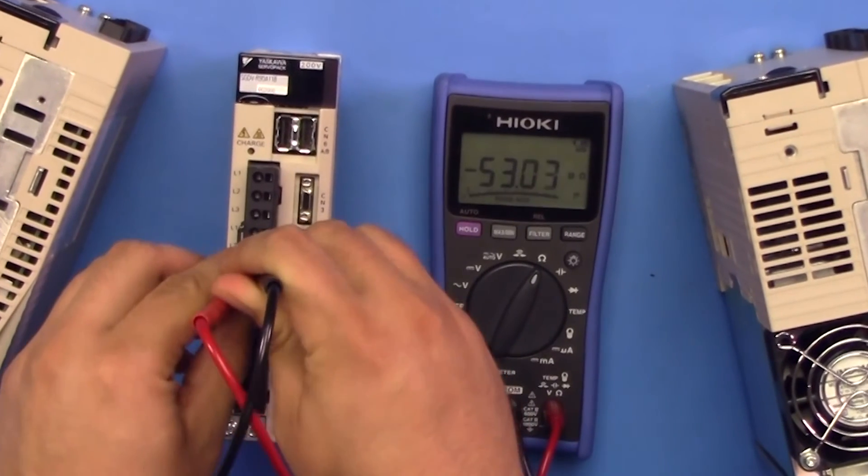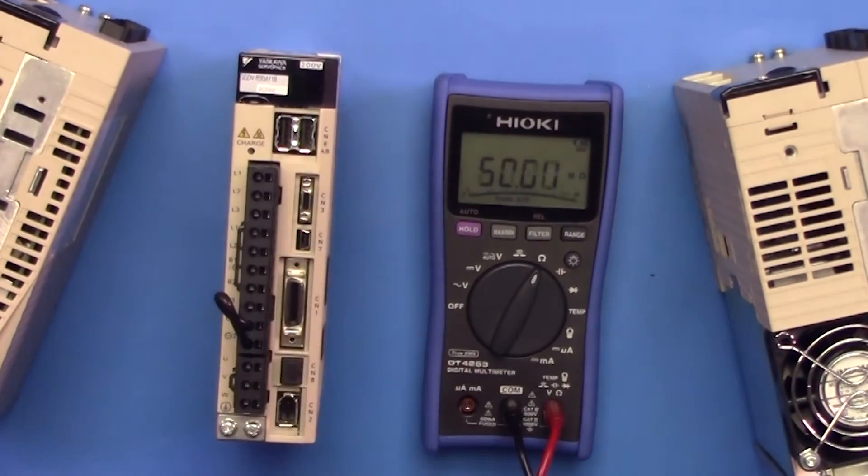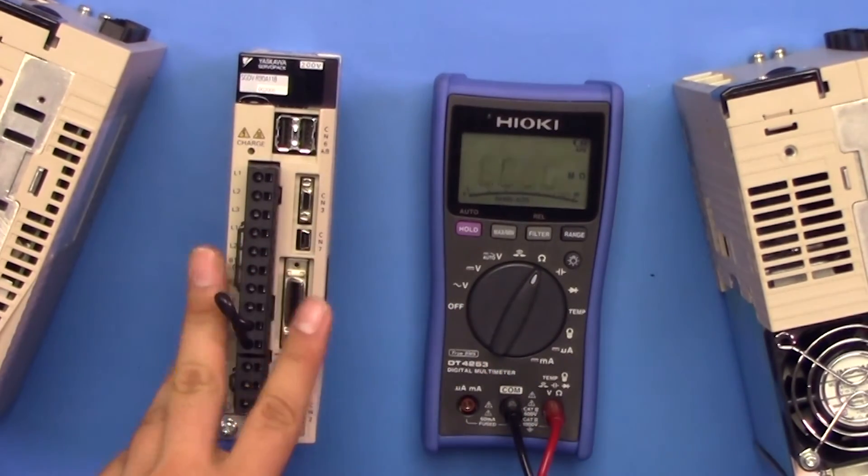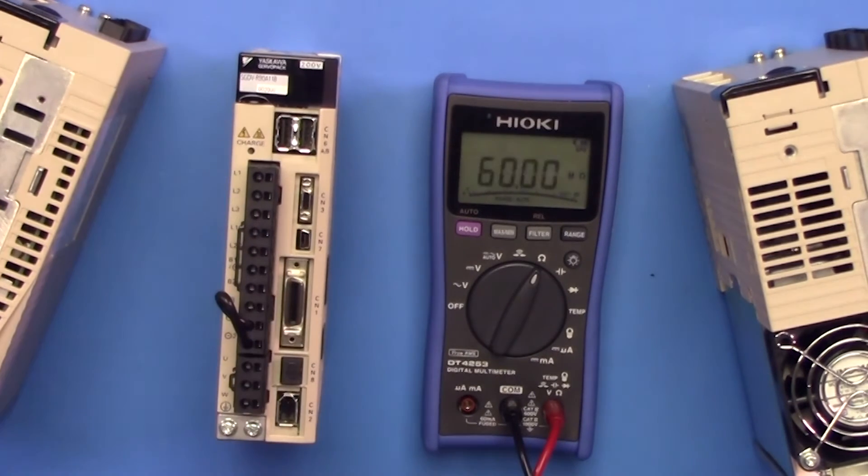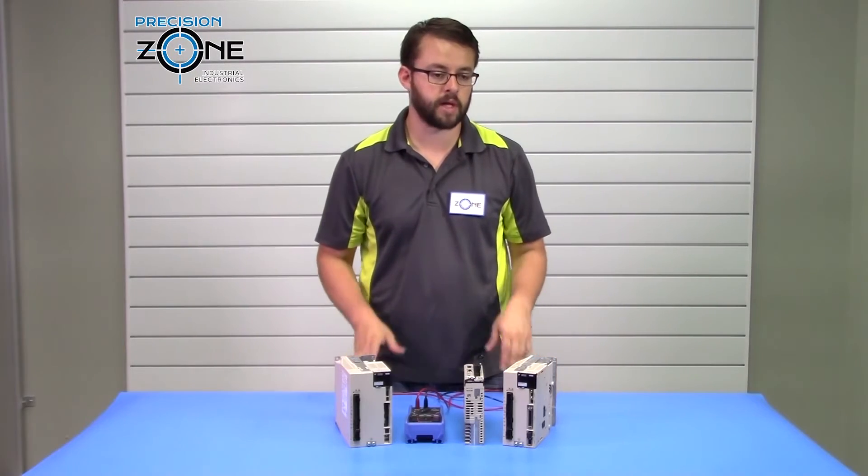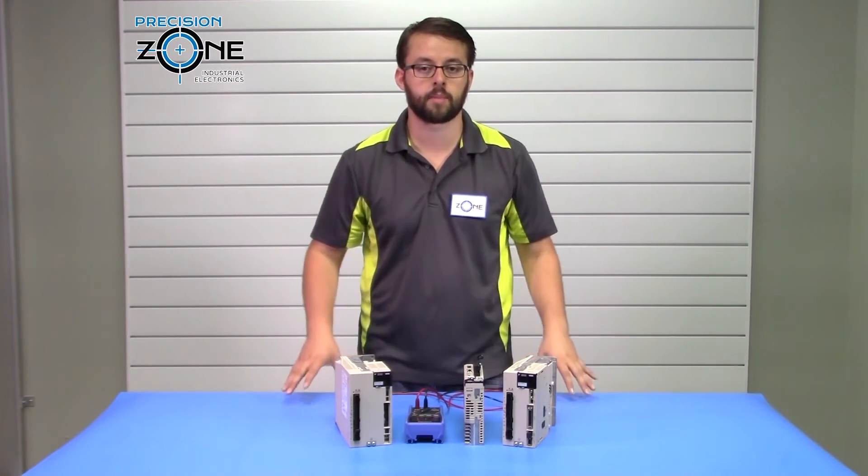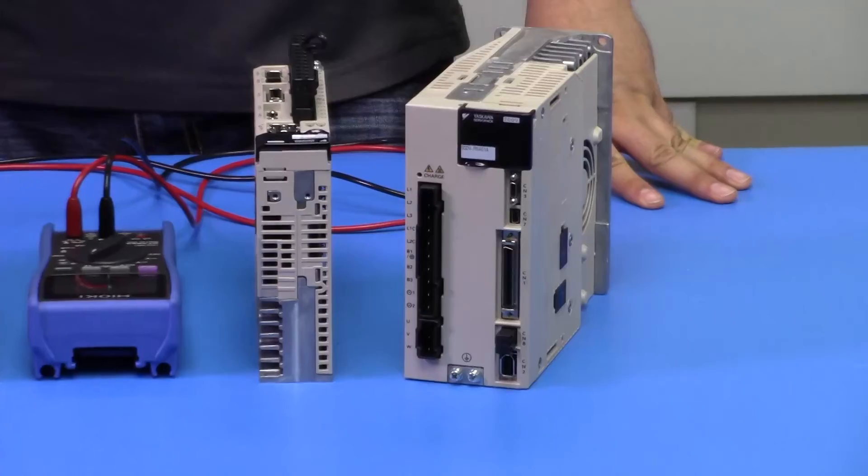So for this application, the regen resistor is external. So you just want to verify that it has not been shorted out. As long as that's the case, it should be in good condition. You can measure the resistance of your external resistor, and it's going to vary depending on the capacity of the drive as well.